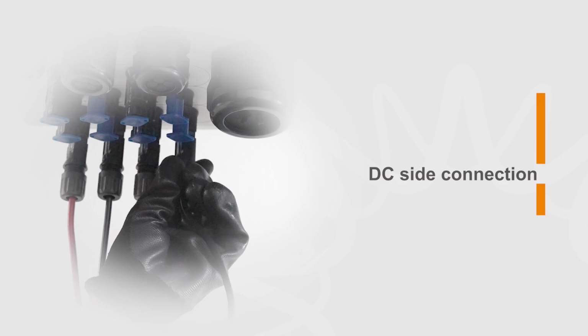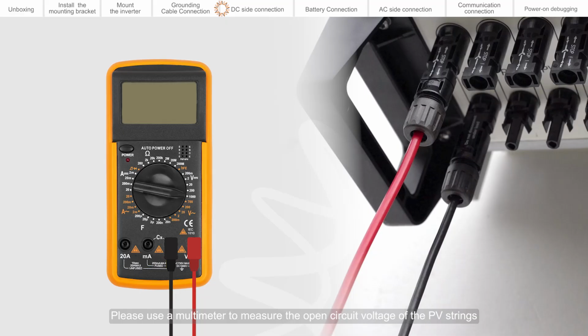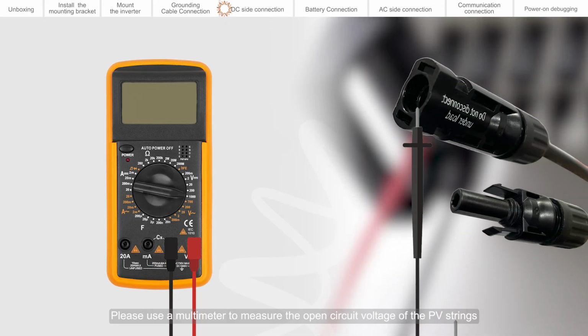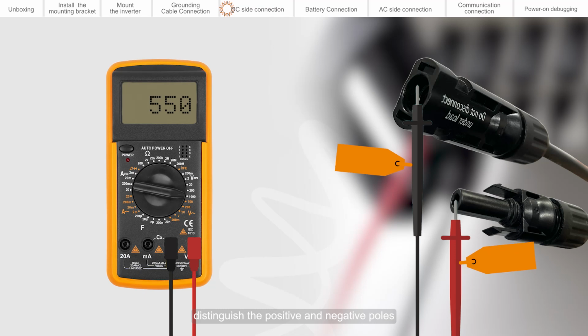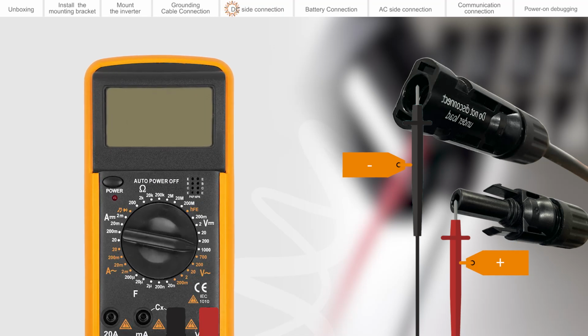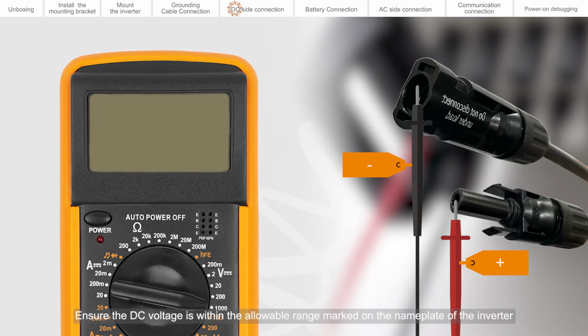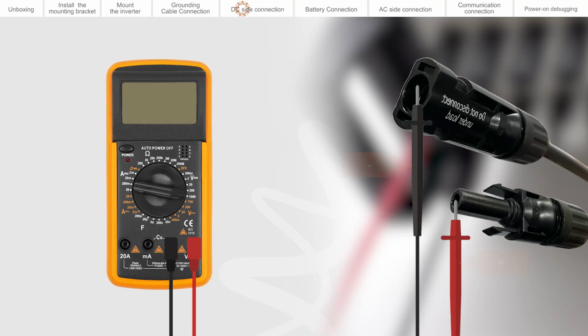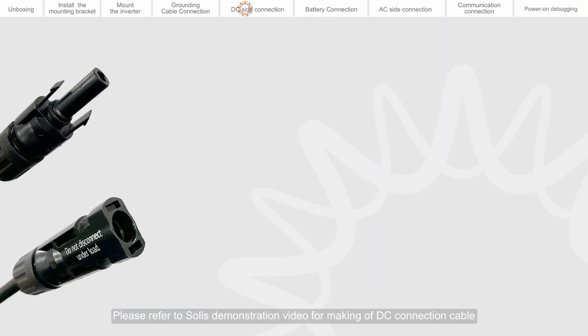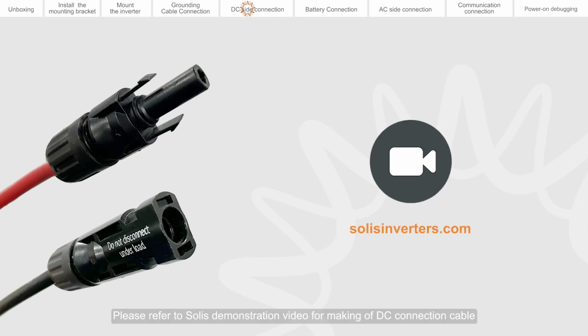DC side connection. Please use a multimeter to measure the open circuit voltage of the PV strings. Distinguish the positive and negative poles. Ensure the DC voltage is within the allowable range marked on the nameplate of the inverter. Please refer to Solis demonstration video for making of DC connection cable.